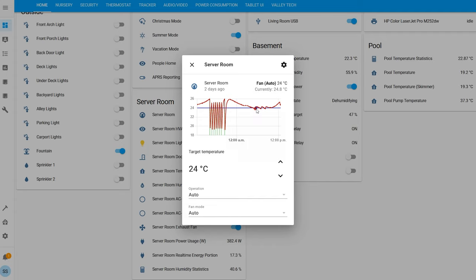The fan cycle curve is much tighter, like a normal thermostat, because the fan is at 100% efficiency as soon as it's on. I keep the server room set at 24 degrees Celsius — it's a little on the warm side, but trying to save power. During the winter it'll be a lot easier and I can probably set the temperature lower.